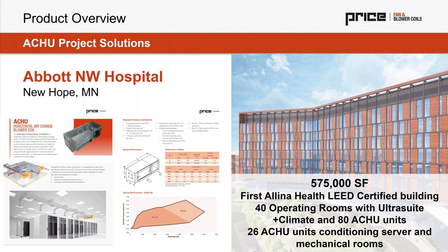So they wanted to elevate the supply air volume and with that also elevate the supply air temperature and cooling. The other byproduct of that, which was managed very well, is that surgery uses a lot of cauterization tools for sealing of internal lesions. So instead of stitches, it would use cauterization tools that actually create and accumulate smoke within the room. So cauterization smoke, which is a little gross, so I apologize for that. But that product was developed in order to increase those air change rates.